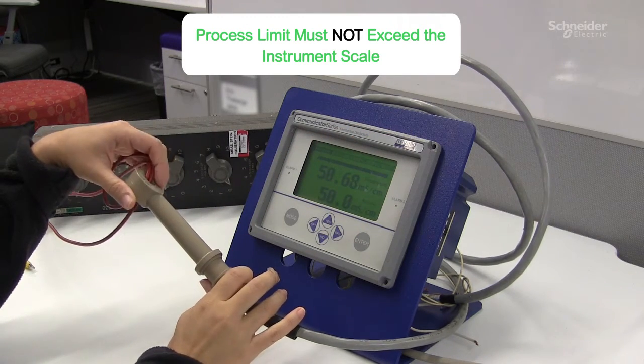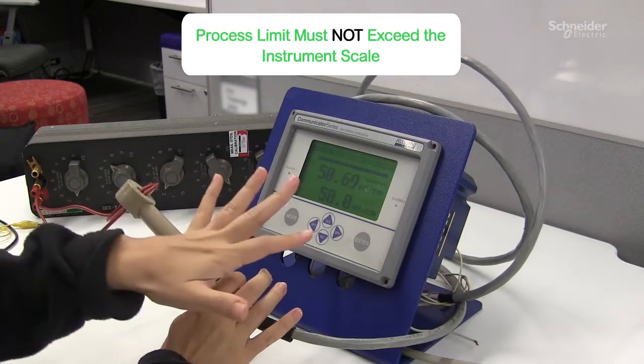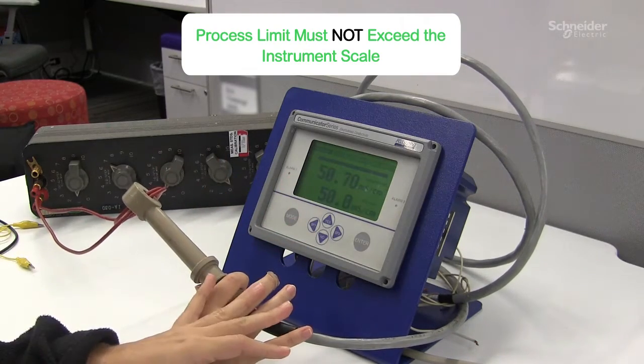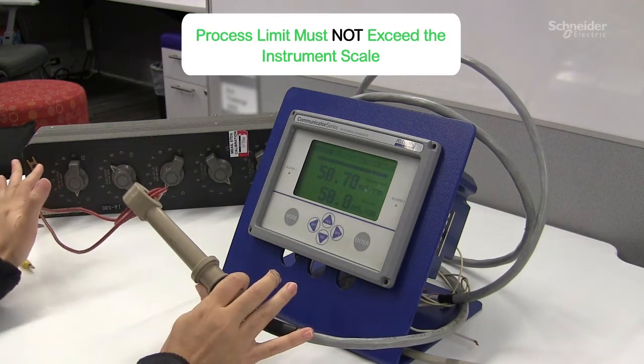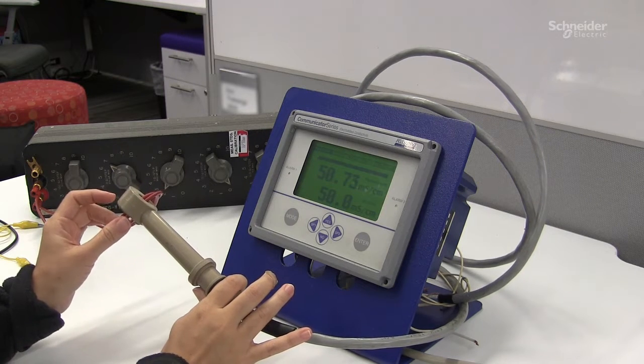So if for example our range had been 30 instead, I still want to select the scale to be 50 in order to cover my whole range. So after you have done this you want to test your calibration and that's why I have not disconnected the decade box just yet.